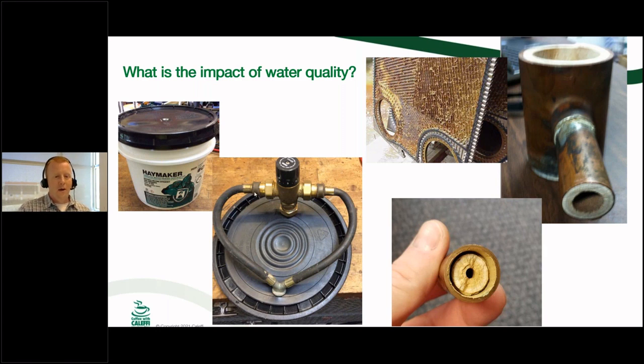Okay. Now I stole this picture from Bob, so I hope Bob doesn't mind. He rigged up this little contraption here where he was using a domestic hot water tankless coil cleaner, a descaler kit from like a tankless water heater, and he used a Y hose here and ran it through that mixing valve to clean it out, and that's perfect. Okay, you've got a mixing valve there, you can do that quick hot swap. We've got the unions on our valve, you can pop them in and out really quickly, clean up that one that you just pulled out and leave it sit there, wait, and again, do it the next year, and keep on going.